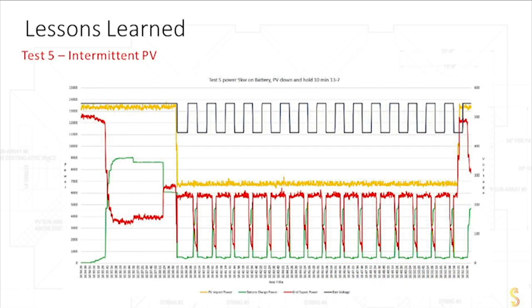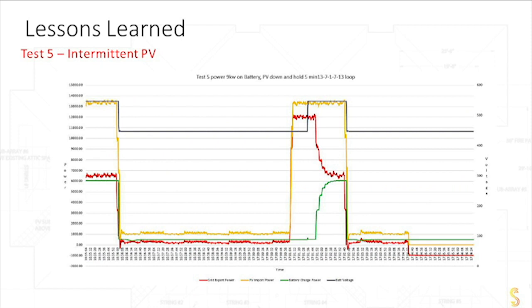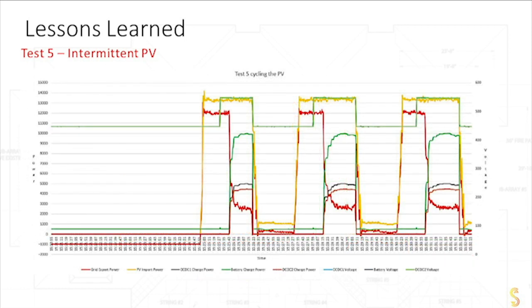Finally, test number 5, the last one, is the one I mentioned earlier, how PV can be very intermittent. It can turn off, it can turn on, it can ramp slow, ramp fast. So this is sort of like a stress test. We just want to see if we can break the functionality of the non-import firmware that we've been talking about. So this is like a little kid with a bunch of dials in an operating center: turn everything on high, turn everything on low, turn the battery on high and the solar on low, and the solar on high and the battery on low, and vice versa, and just see if we can break this thing.